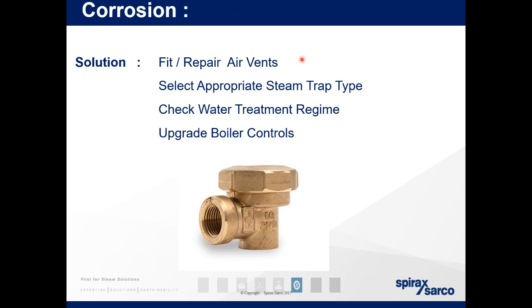Check water treatment regime. Again, by checking the quality of the water in your boiler through boiler tests, the more you check it, the more accurate you can be with your chemical treatments. And upgrade of boiler controls. This refers again to the on-off controls versus modulating. So at this point, do we have any questions?